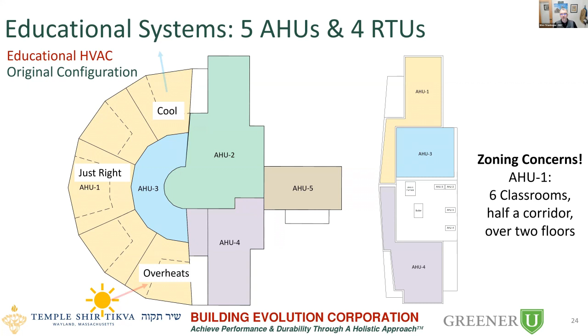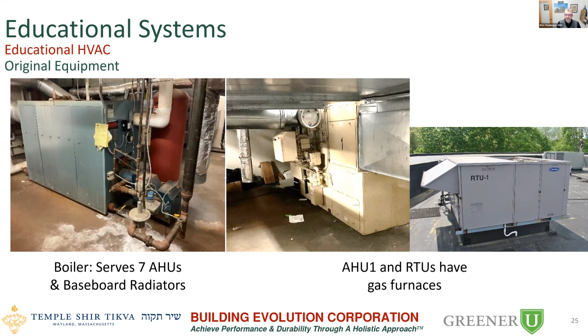And looking at the types of systems: boilers on the left-hand side, and in the middle, a hot deck, cold deck system, if anybody's ever heard of those. That's a furnace that burns natural gas while simultaneously providing cold air, mixing the two air streams together to try to maintain the temperature of the space. I wouldn't say that's a high efficiency system. And then there were the old RTUs on the roof, which are furnaces. So it was a good opportunity for the buildings to do an upgrade.